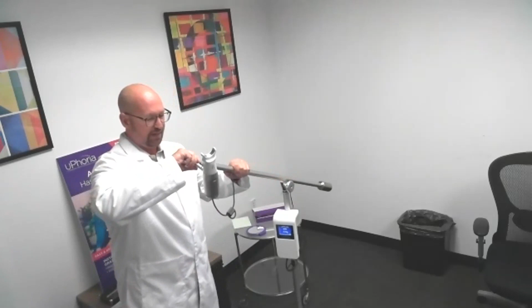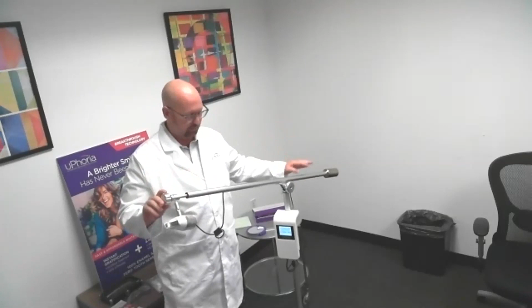This machine itself, the system elements: you have the mouthpiece, you have the ultrasonic unit, and you have a plunge mechanism with the stand. So you simply push in, and you can do quarter turns to give you major movements. You have the horizontal and vertical bars. This knob here, I tend not to have to loosen or tighten once I do it once. Typically it'll stay in position, and once you tighten that, you're pretty much good to go. When I put it up to a patient, I'm turning the outer knob, letting it hang down, and then I can position it around like that and tighten it up. You really don't need to do the quarter turns or the plunge that often, because you're typically going to find where it is sitting vertical to the floor. But this outer knob, you can loosen it and move it around. It gives you the degrees of freedom to have it up to the patient.